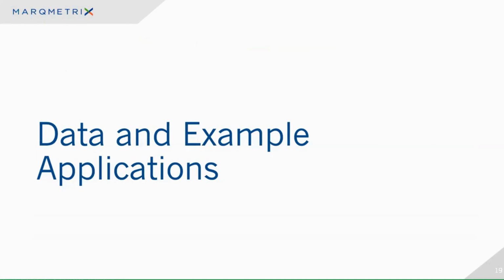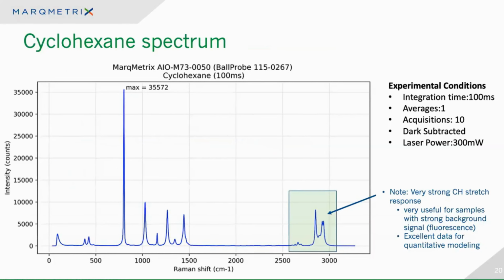I want to quickly go through a little bit of data, and then we'll finish with some calibration work. Give you an idea of the spectral range and resolution of our system. Here's a cyclohexane spectrum. This is collected at 100 milliseconds, one average, so there's no averaging. We have 10 acquisitions that are overlaid, dark subtracted, looking at the laser at 300 milliwatts. One thing I'd like to point out is our spectral range is quite good, about 75 wave numbers to about 3,250 wave numbers. We'll see a little more of that in the next slide.